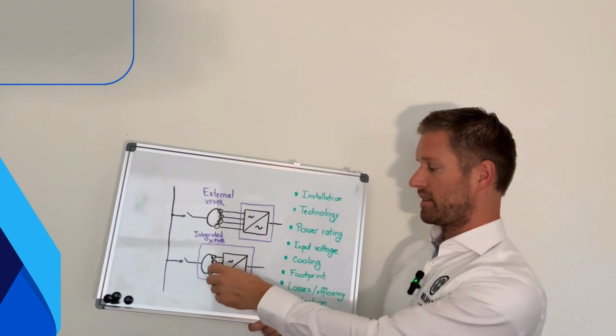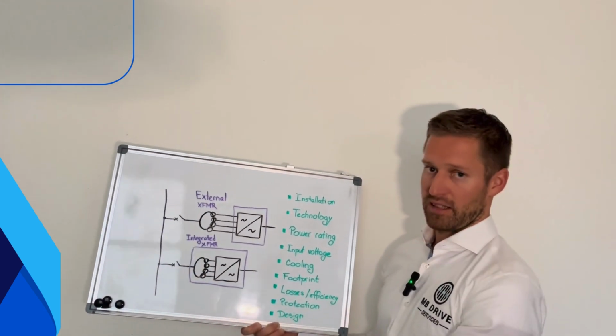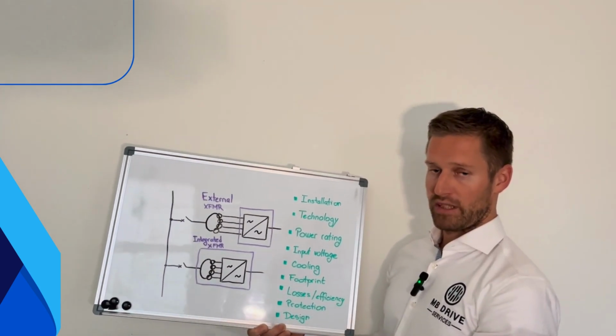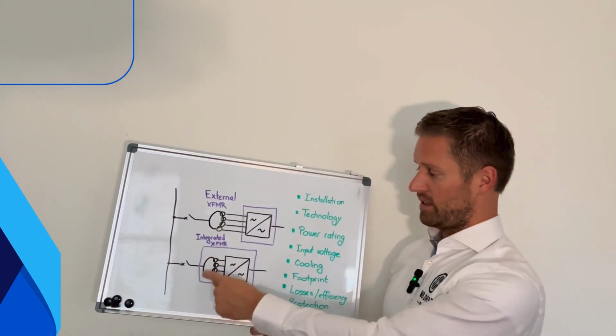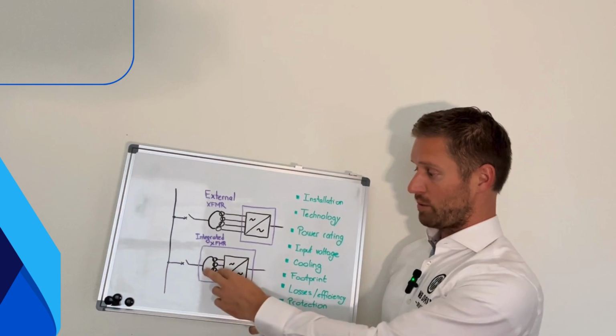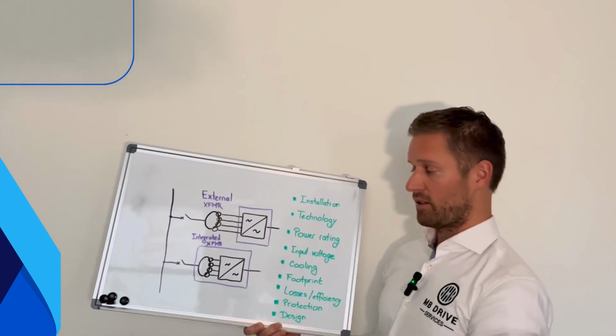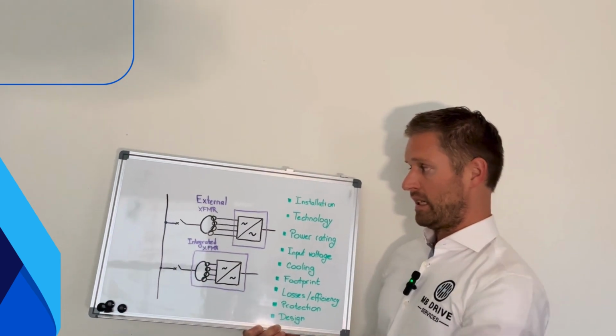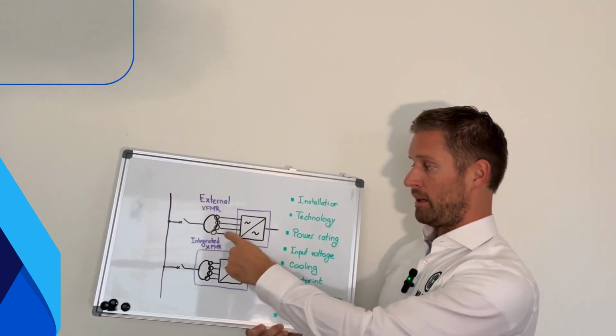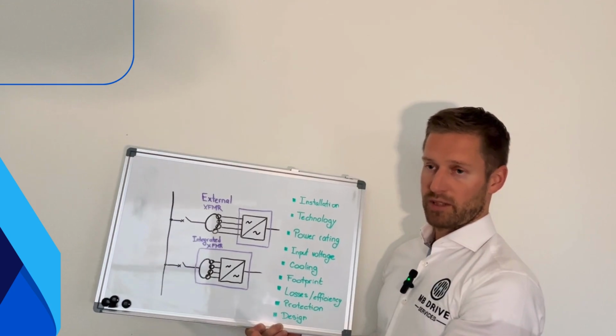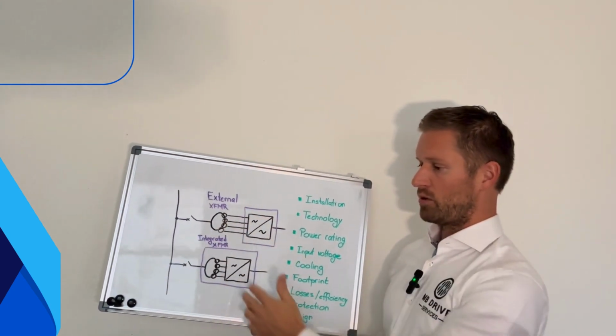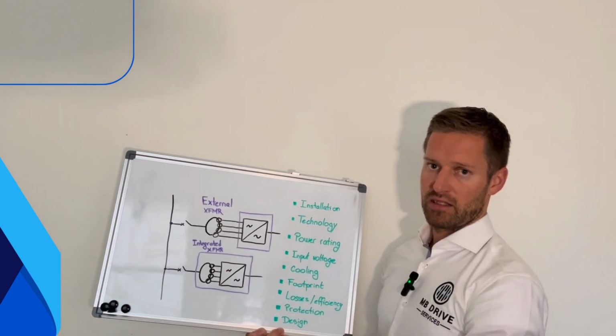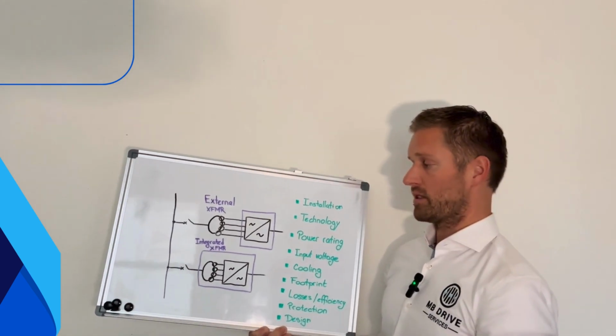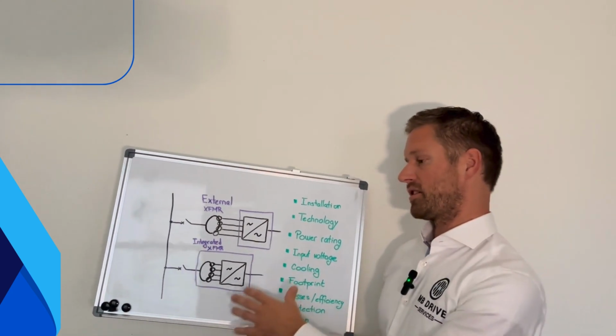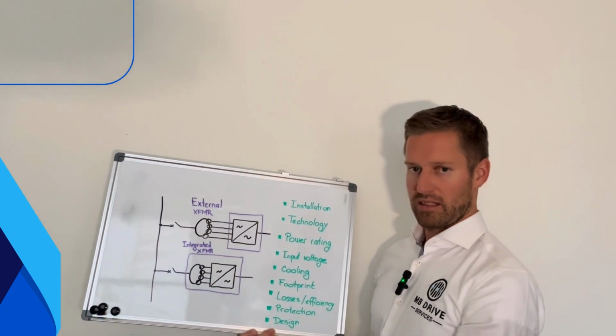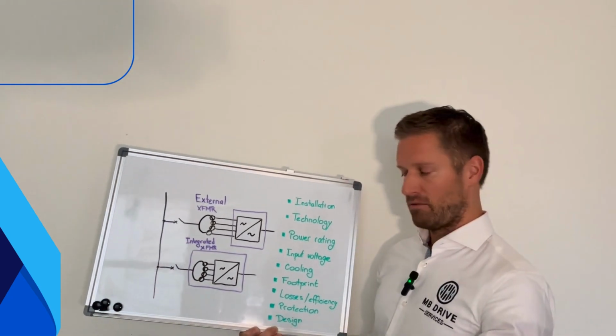Footprint: the integrated transformer, as it's part of the VFD, is inside the electric room. There we might be more restricted with the space, so the footprint here is optimized. Or let's say the transformer is designed to have as little footprint typically as possible. With the external transformer, we have the flexibility, we can do it project specific. If it's standing outdoors, then typically the space limitation is not so critical. There might be, of course, exceptions, but in most of the installations when it's standing outdoors, it's not so critical whether it's half a meter wider or not.